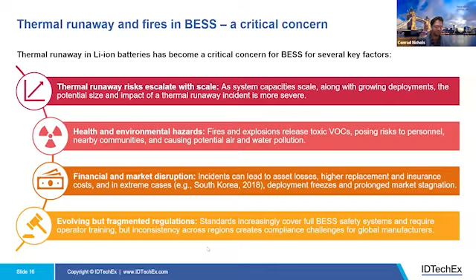So what causes thermal runaway, and what are its stages? BESS failures can stem from a range of internal and external factors, which might trigger a thermal runaway event and in some cases lead to a fire. Causes of battery thermal runaway include electrical, thermal, or mechanical failures—things like overcharging, heat stress, or damage to the battery itself.